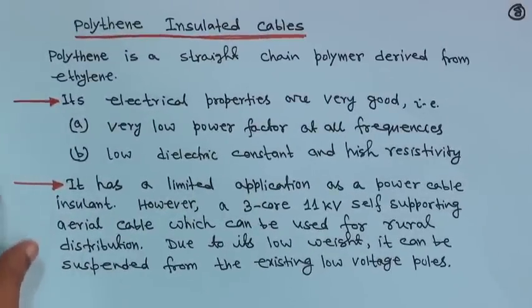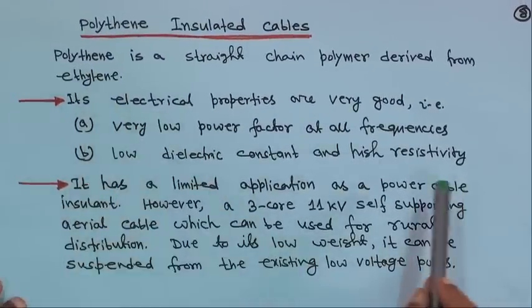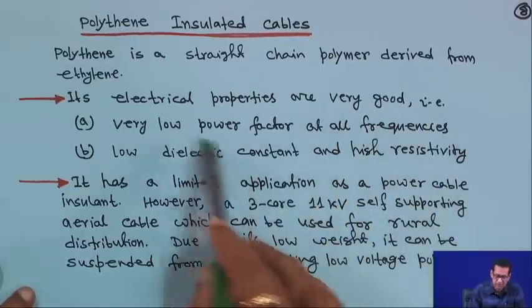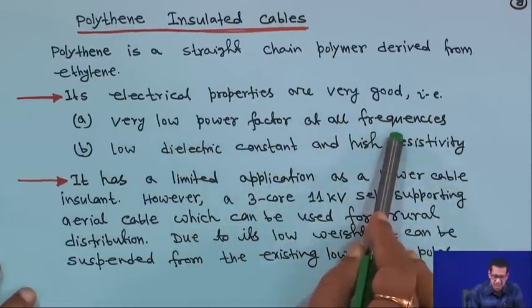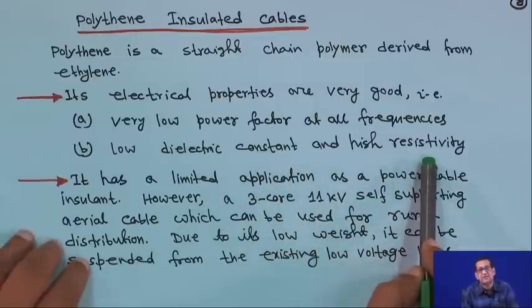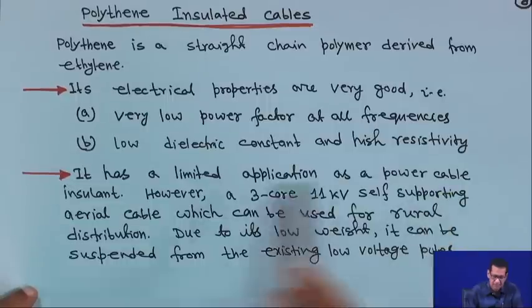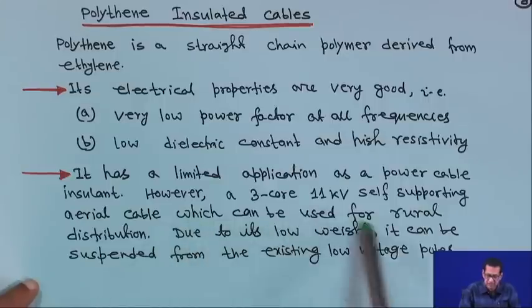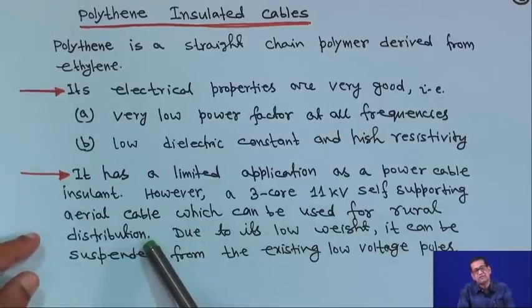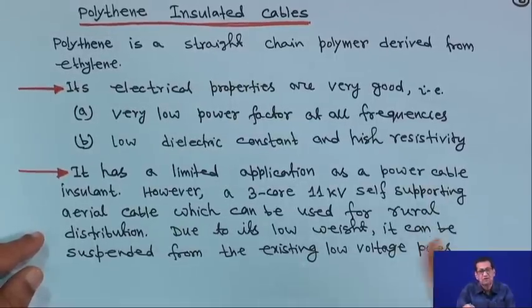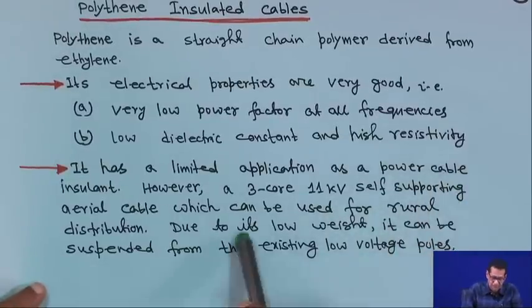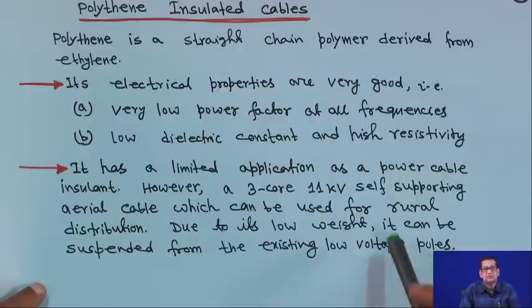Polythene insulated cables — polythene is a straight chain polymer derived from ethylene. Its electrical properties are very good: very low power factor at all frequencies, low dielectric constant, and high resistivity. It has a limited application as a power cable insulator. However, a 3-core 11 kV self-supporting aerial cable can be used for rural distribution. Due to its low weight, it can be suspended from existing low voltage poles.